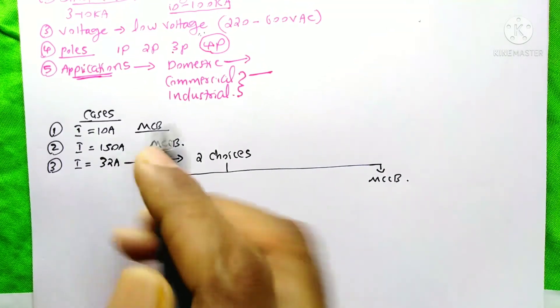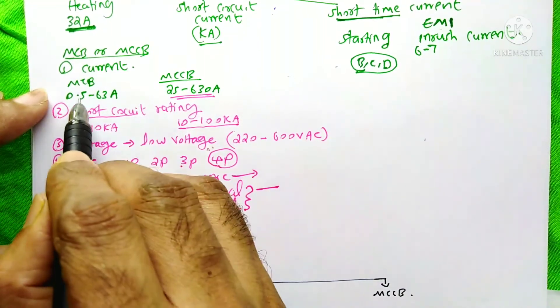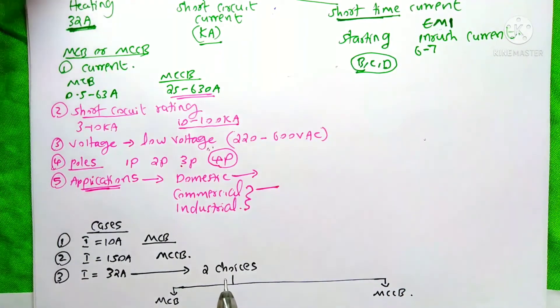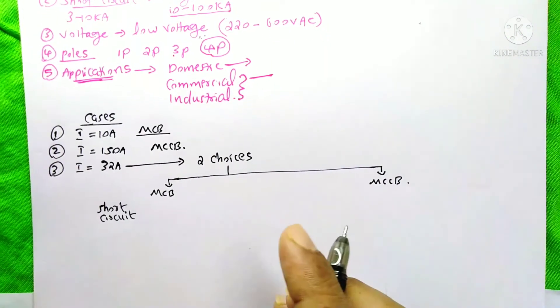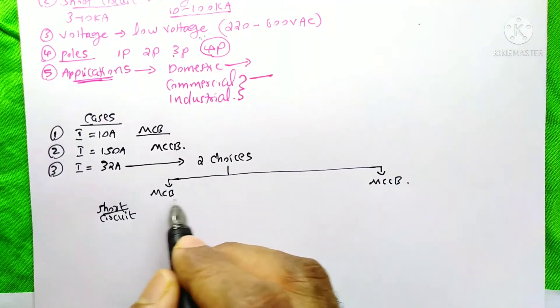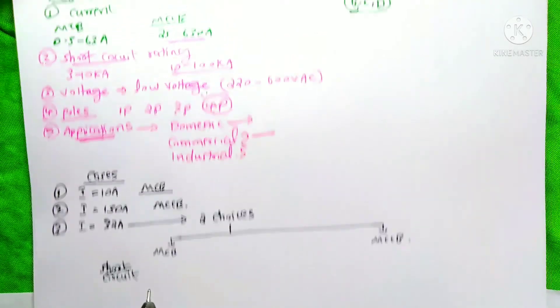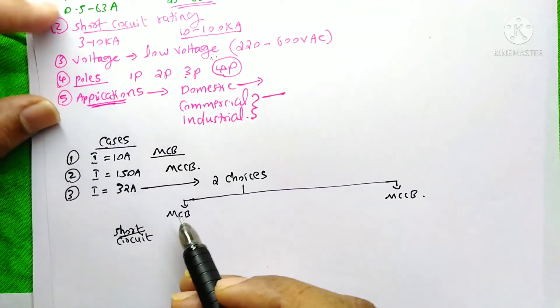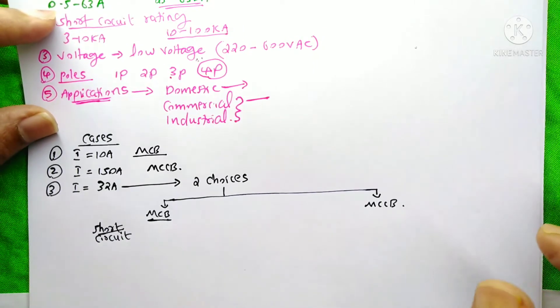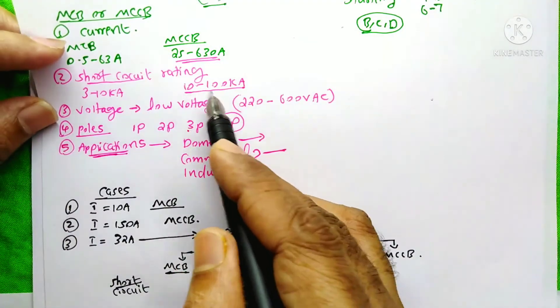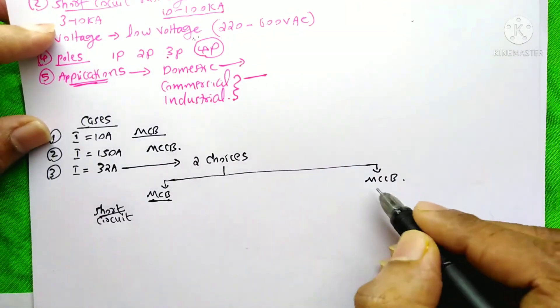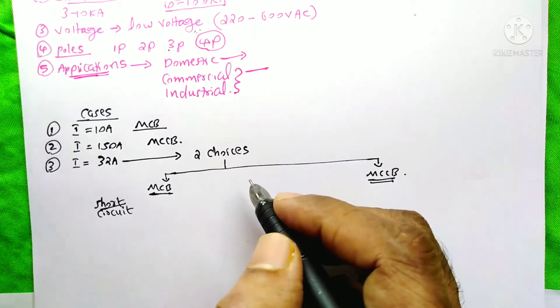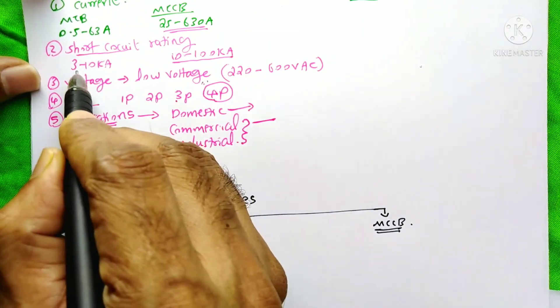The next case is if the circuit current is 32 amperes. Both MCB (0.5–63 A) and MCCB (25–630 A) cover this range, so you could select either — there is no problem. The next factor to consider is the short circuit current. If the short circuit current is less than 10 kilo-amperes, you can select the MCB, whose range is 3 to 10 kilo-amperes. But if the short circuit current is more than 10 kilo-amperes, that falls in the MCCB range, and you must select only the MCCB.